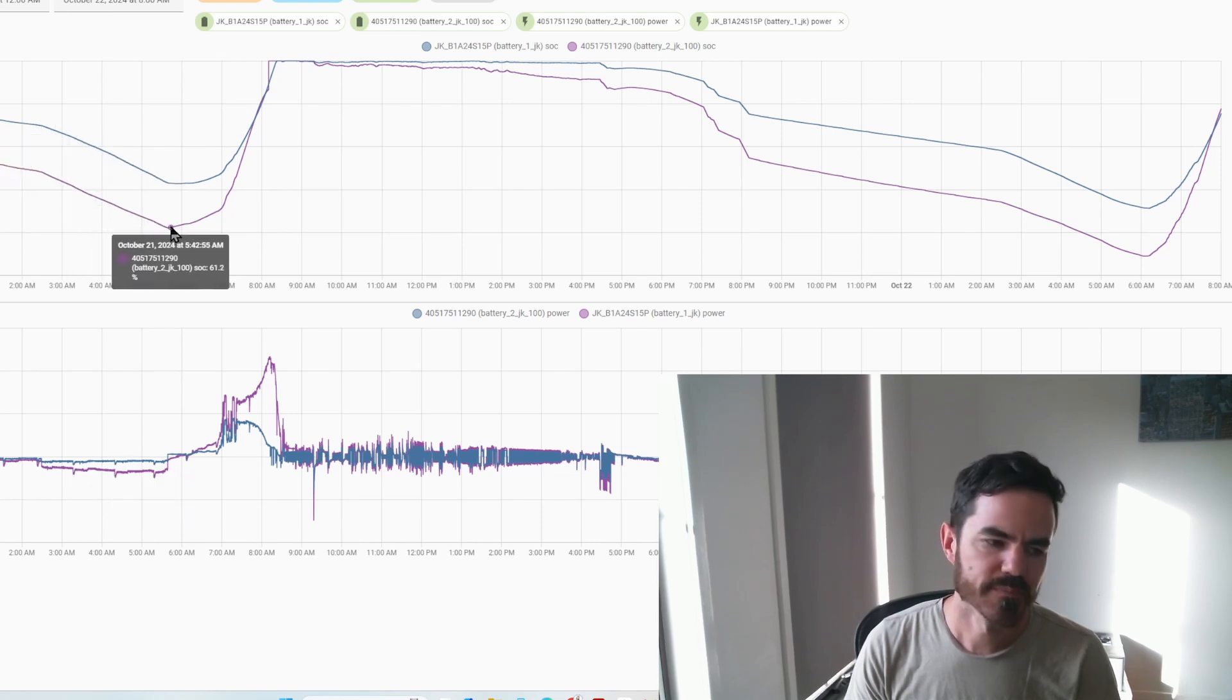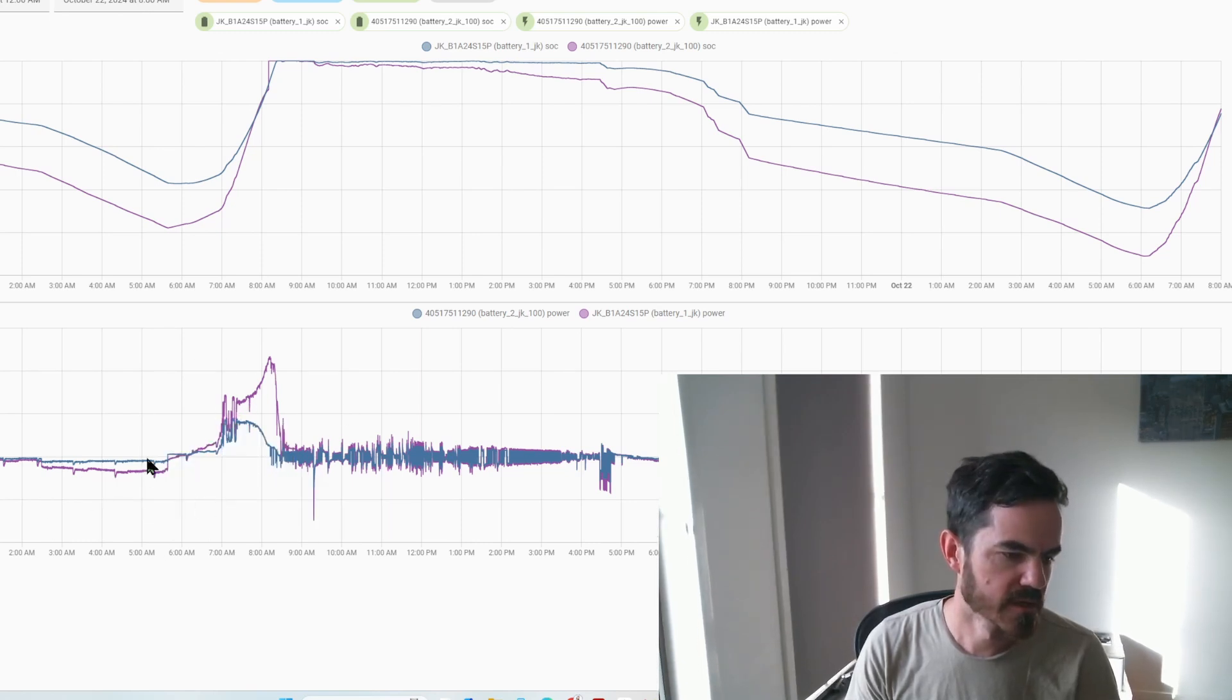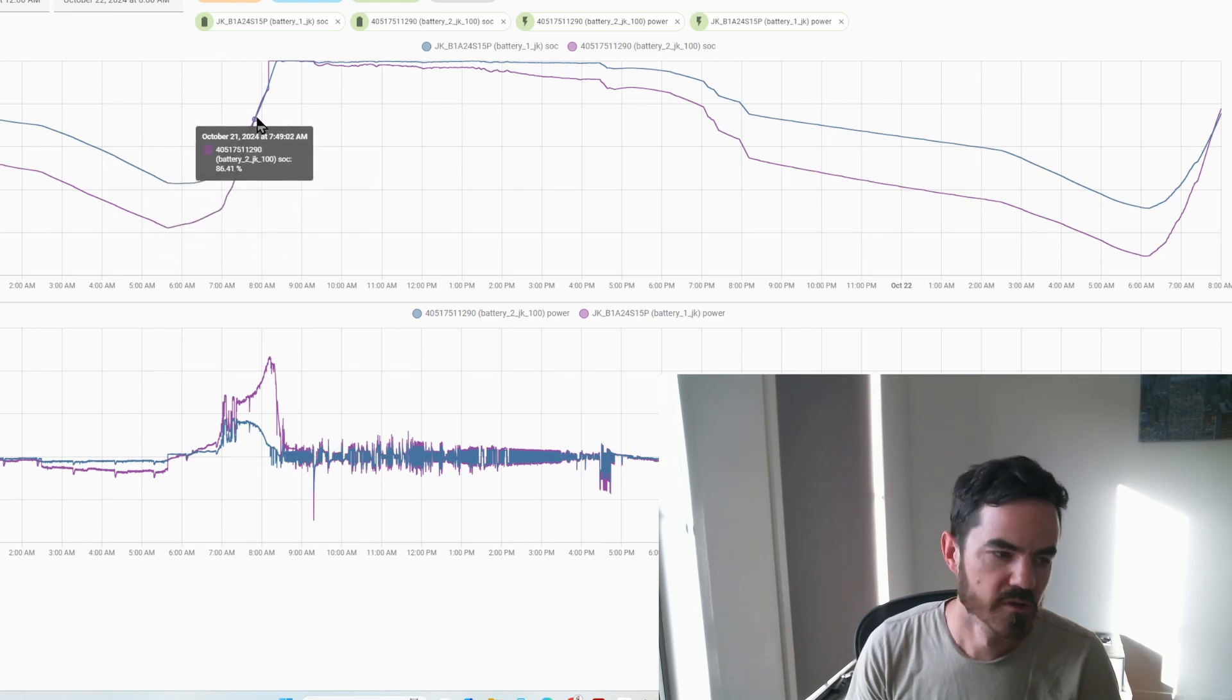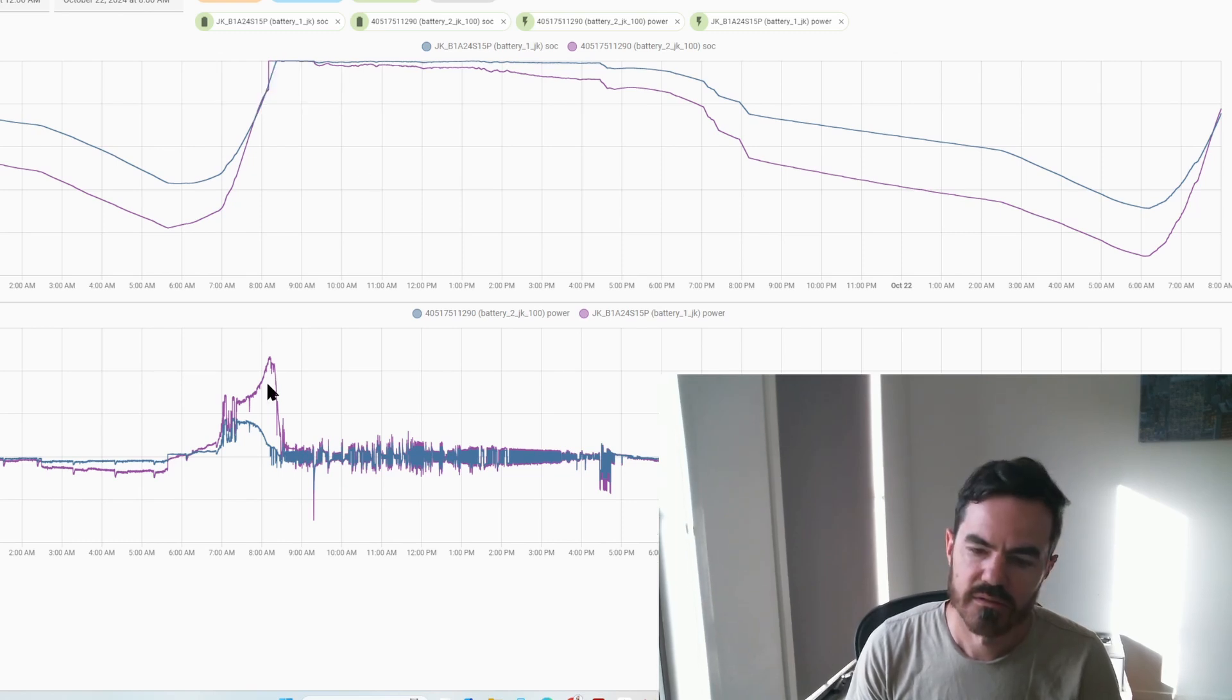But you'll see down at 6am when they start charging again, very quickly, this is when it starts charging. This is the current, the power going in and out of battery down here, and this is the actual state of charge. Down here you can see that at 7:30am battery one is getting a lot more current put into it, like by 8am it's getting 4500 watts and this one's still only getting 734 watts. You can see how this one started dropping off here while this one was getting a lot more current, and that's how it kind of catches up. If you look at the top here they start to converge. Battery 2 JK 100 will quickly catch up percentage-wise and be converged with battery one, so they both fully align and get balanced. At the very top here they're both charged around the same time to 100%, so they kind of just balance each other out.